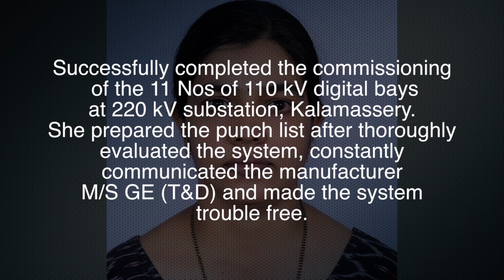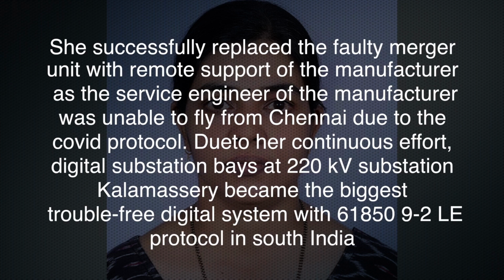She has successfully completed the commissioning of 11 numbers of 110 kV digital bays at 220 kV Substation, Kalamassery. She prepared the punch list after thoroughly evaluating the system, constantly communicated with the manufacturer, Messrs. GE, and made the system trouble-free. She successfully replaced the faulty merging unit with remote support of the manufacturer, as the service engineer of the manufacturer was unable to fly from Chennai due to COVID protocol.